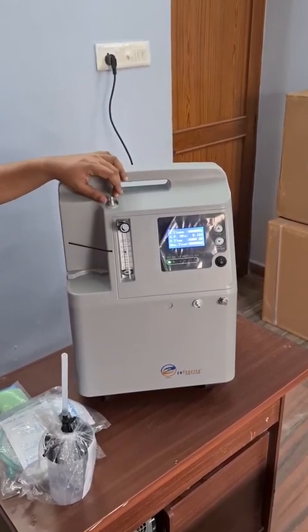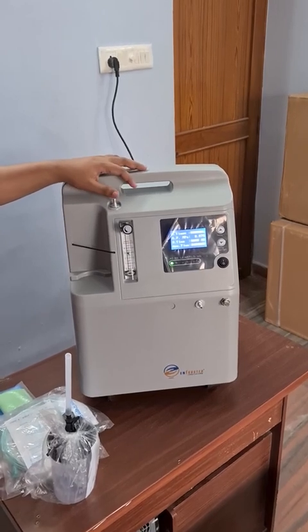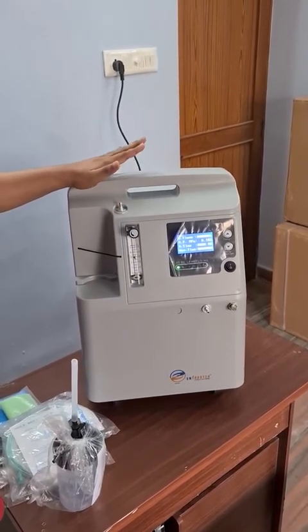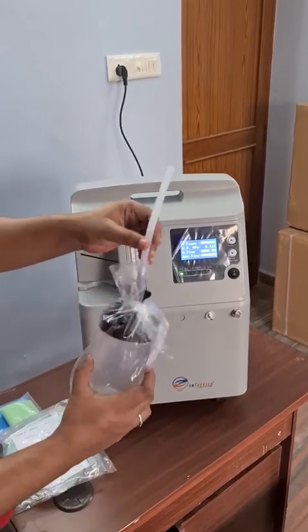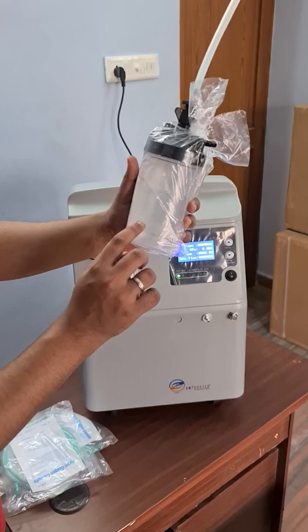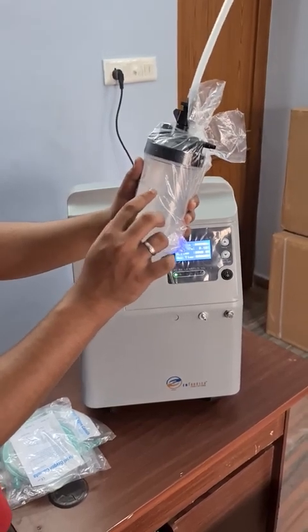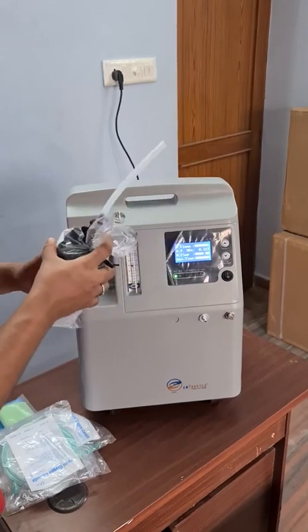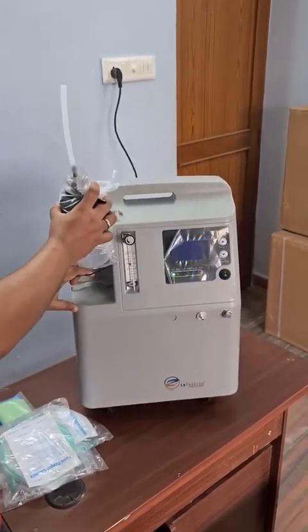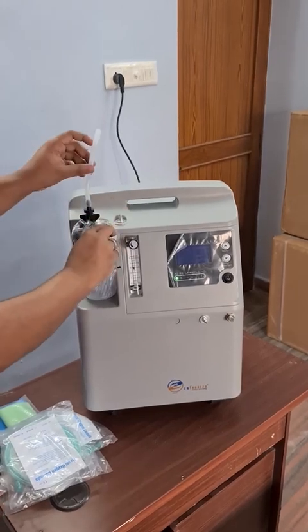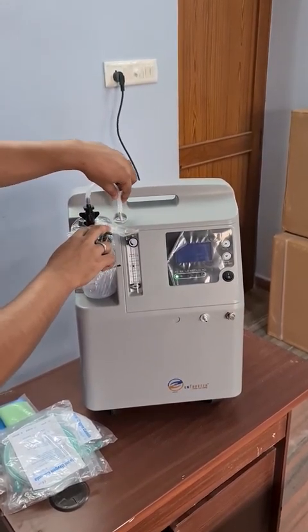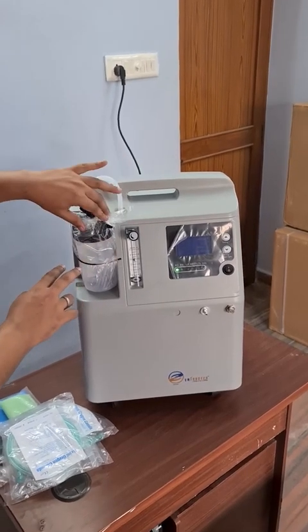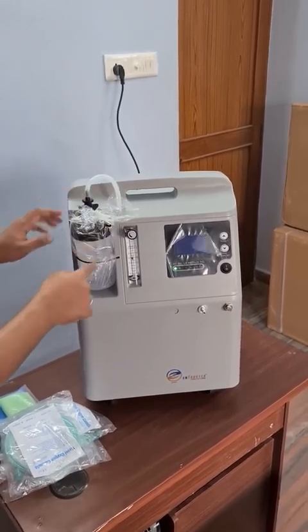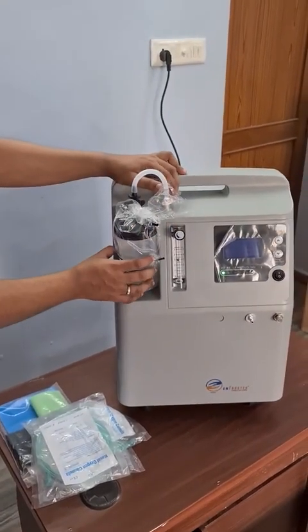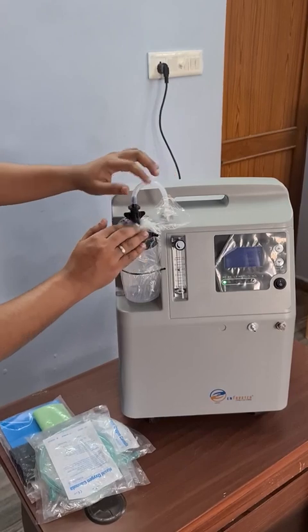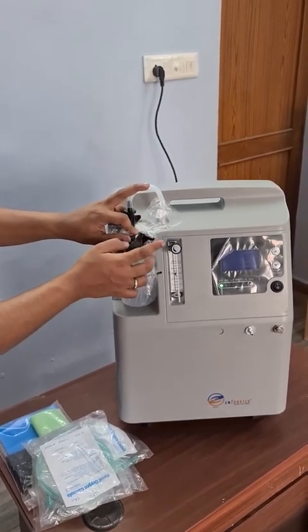Generally, for 90% or even 95% of patients, doctors will advise using the concentrator along with a humidifier. The general practice is to fill the humidifier bottle. There will be 2 markings, minimum and maximum. You can fill water in between both these levels, and that will be sufficient for almost a night. You place the humidifier bottle here, and connect it from the oxygen output port. Oxygen will enter the humidifier bottle, get humidified, and then exit from this particular port of the bottle.